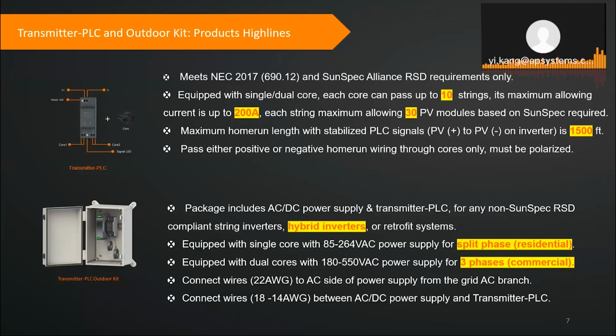Yeah, and actually, sorry to jump in here. Most of the inverters that we're selling nowadays, for example, SMA Sunny Boy, are already SunSpec certified. So you will not need a PLC transmitter kit. It's already integrated in the inverter, which is really nice. And that's the whole purpose of SunSpec, right? It's a communication protocol that is not proprietary, but is shared amongst the different inverter manufacturers and components manufacturers such as AP Smart. So in that case, you don't need to buy a $200 piece of equipment to use your AP Smart on a residential system, which of course is a much bigger deal on a residential system than on a commercial system. On a commercial system, a $200 piece of equipment is not that big of a deal when you're using a 100 kilowatt inverter versus a 5 kilowatt inverter. Correct. Yeah. Thank you.